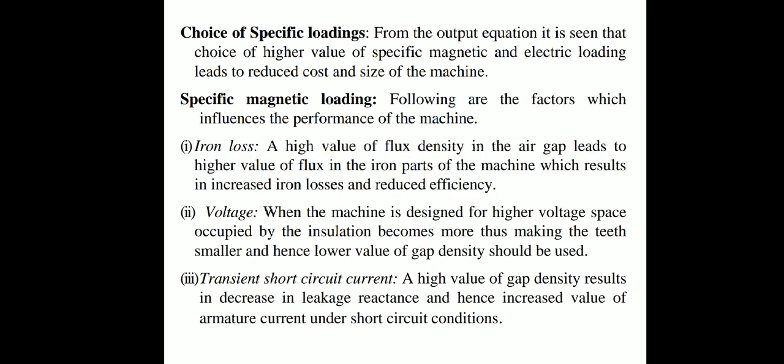For specific magnetic loading, the following are the factors which influence the performance of the machine. First point is your iron loss. A high value of flux density in the air gap leads to a higher value of flux in the iron parts of the machine, which results in increased iron losses and reduced efficiency.